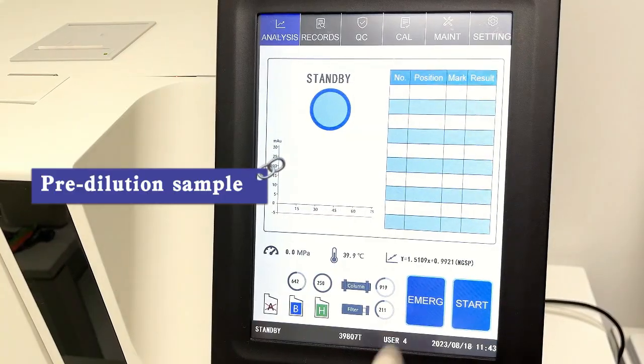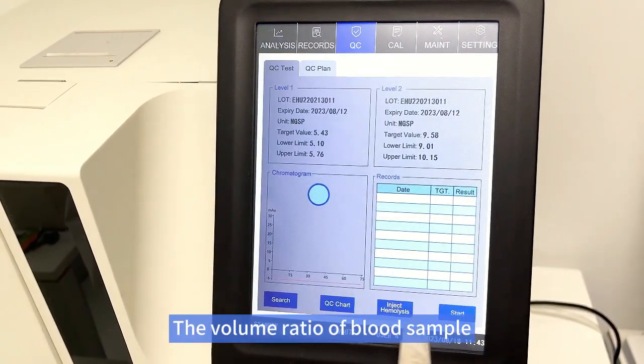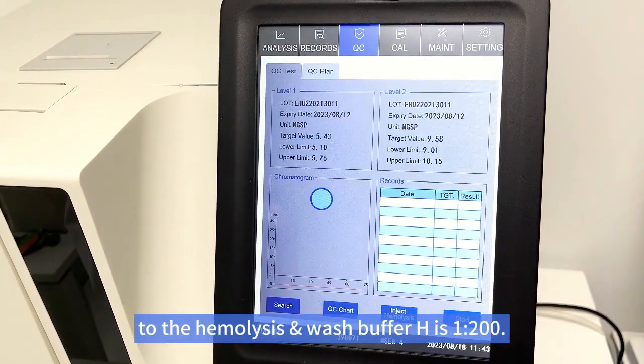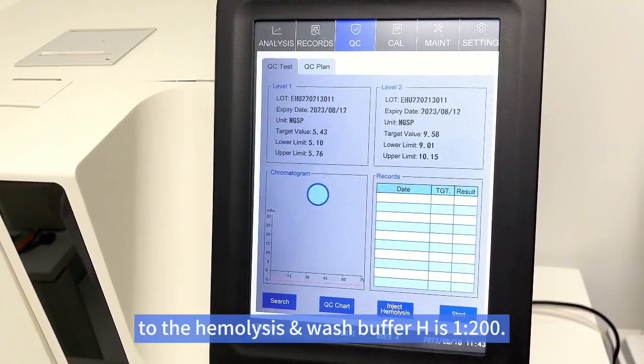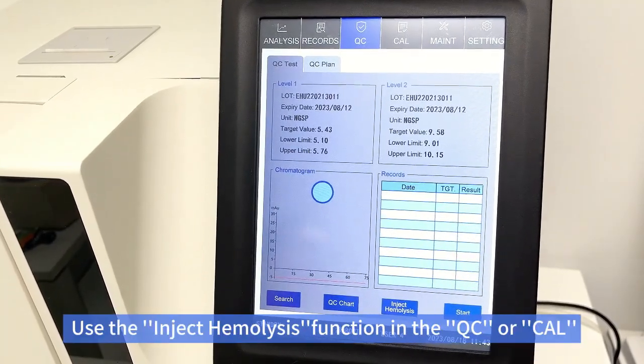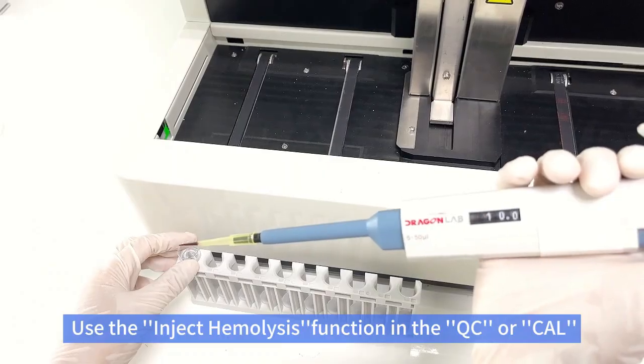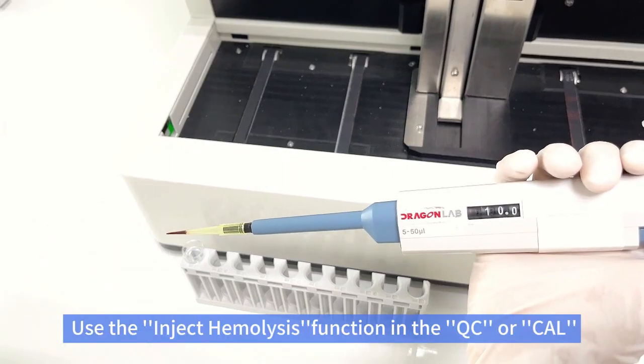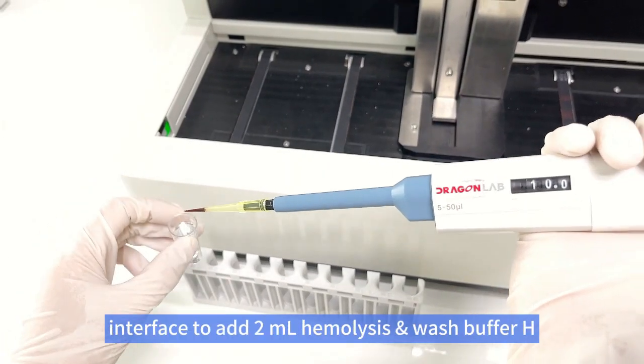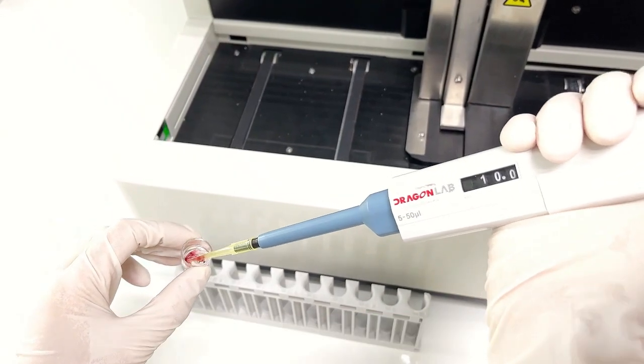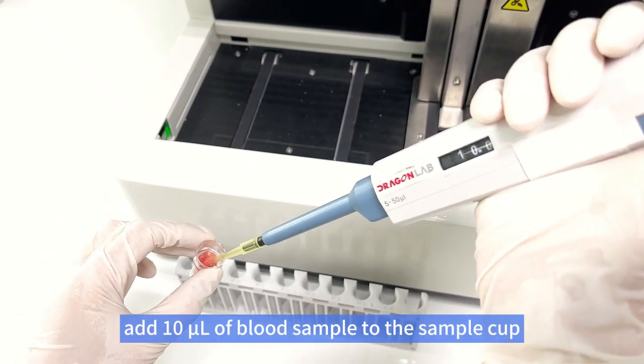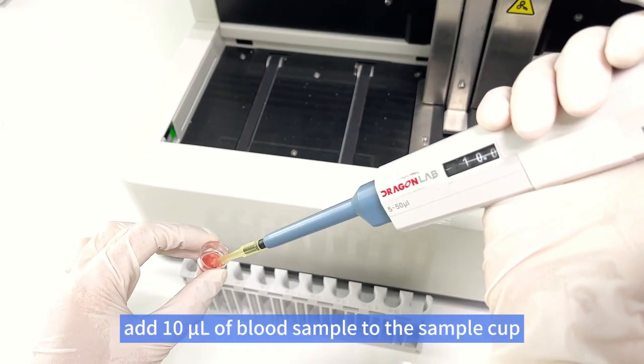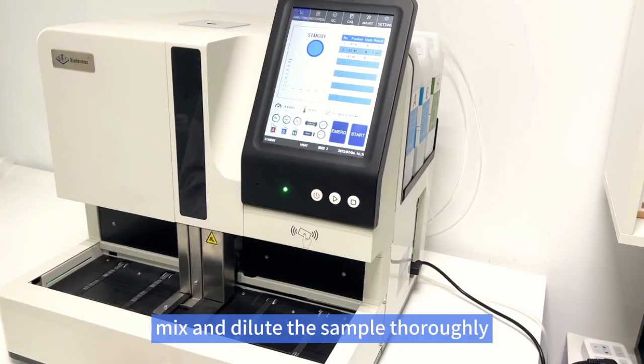for use. Pre-dilution sample. The volume ratio of blood sample to the hemolysis and wash buffer H is 1 to 200. Use the inject hemolysis function, recommended, in the QC or CAL interface to add 2 ml hemolysis and wash buffer H into sample cups. Add 10 microliter of blood sample to the sample cup. Mix and dilute the sample thoroughly.